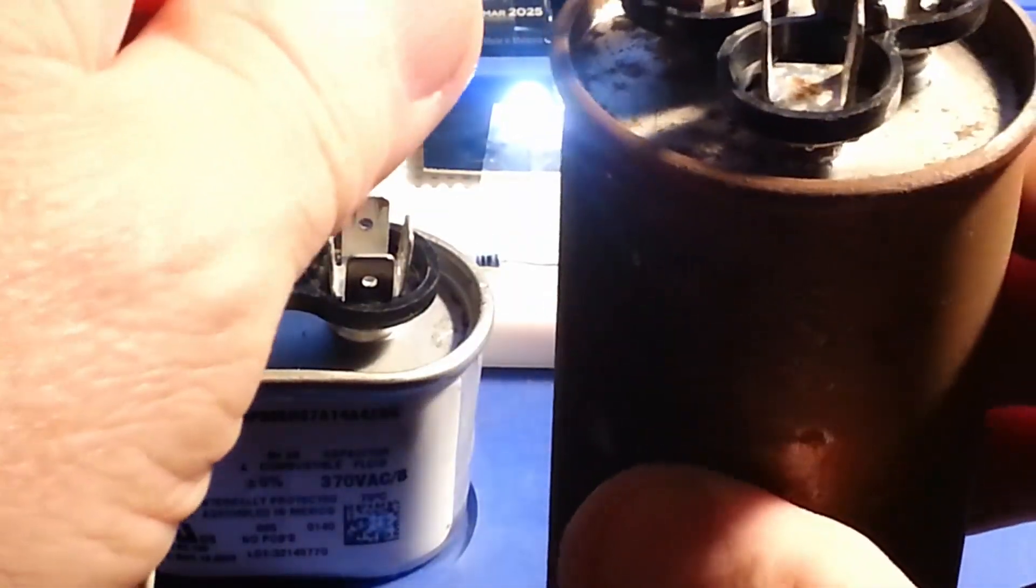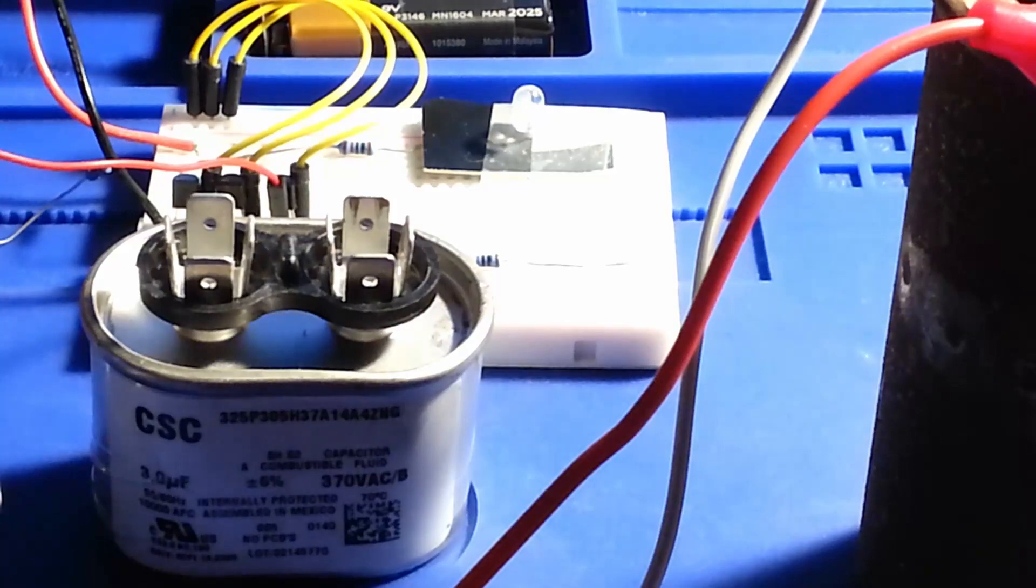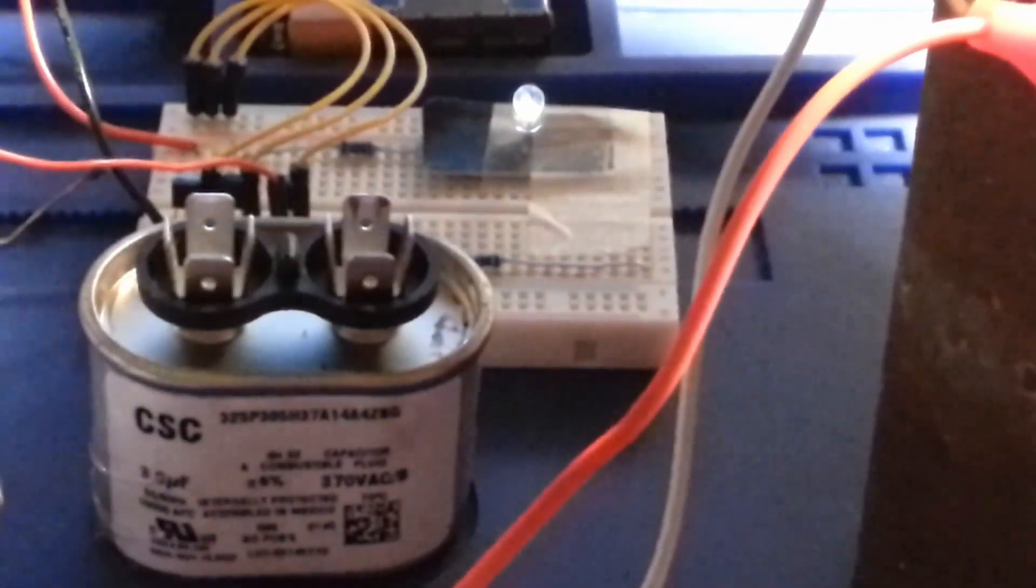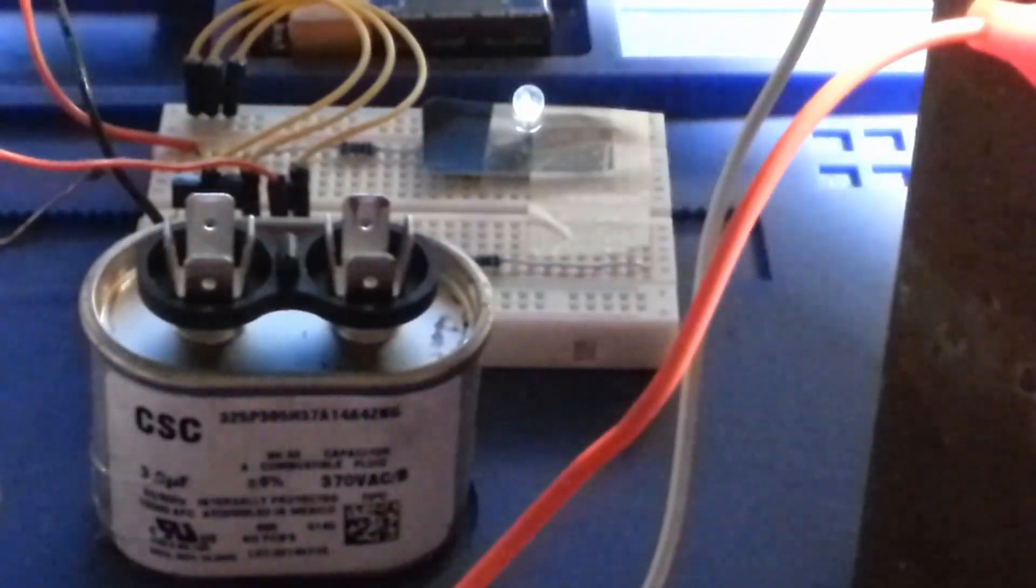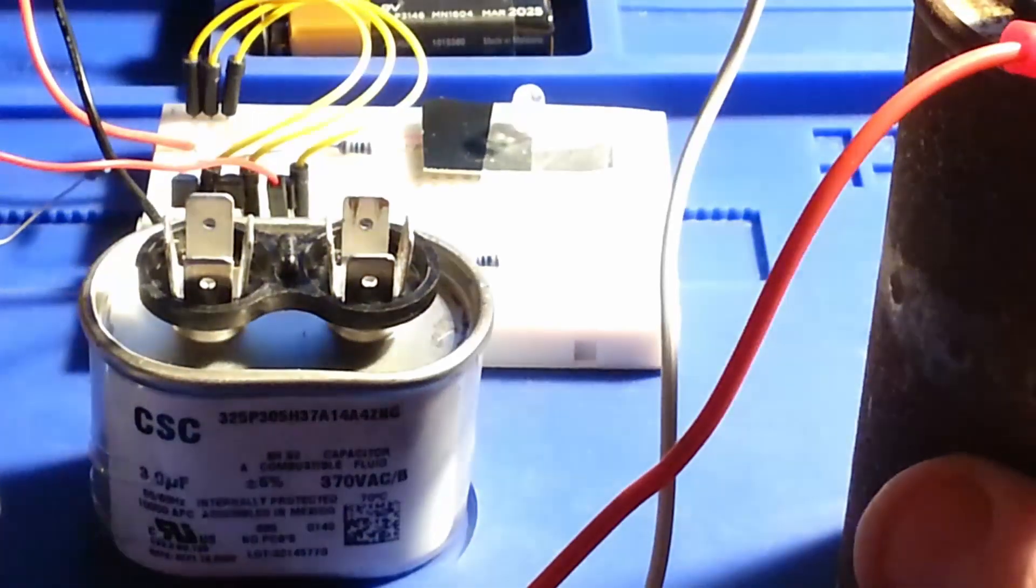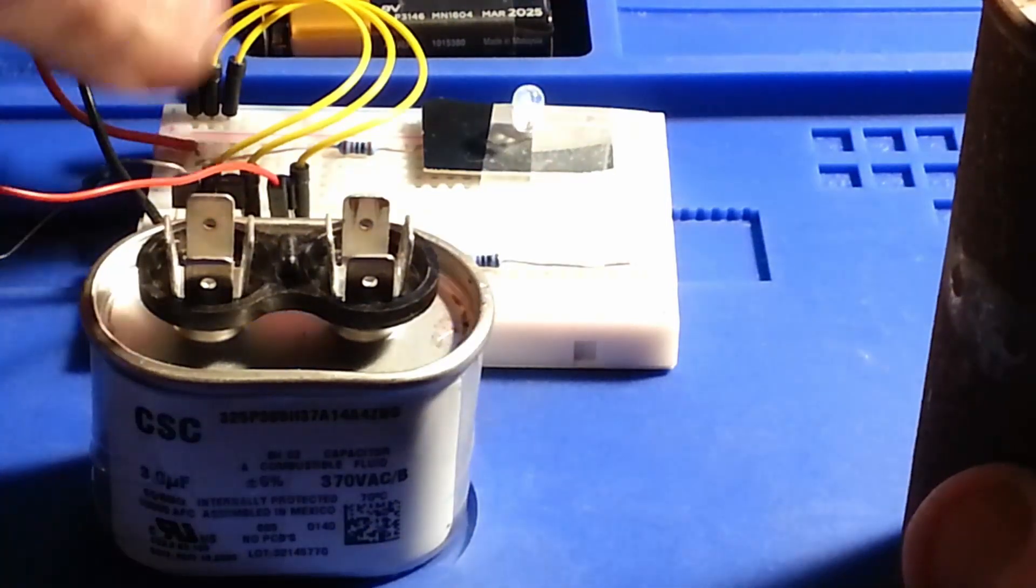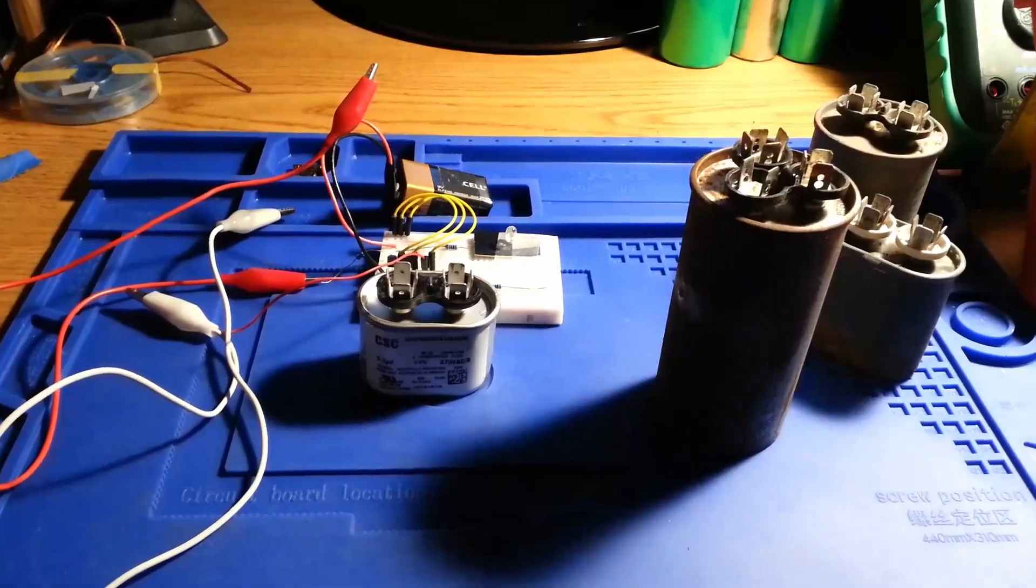And the two section one here, this one has a little bit better metallic case. And as you can see that LED is lit up a little more, so it's starting to get a slight bit more of a fault. But this is still in the gigaohm range, so it would be nothing to be directly concerned about. Now that gets us through a qualitative measurement, and we can go one step further and do quantitative.